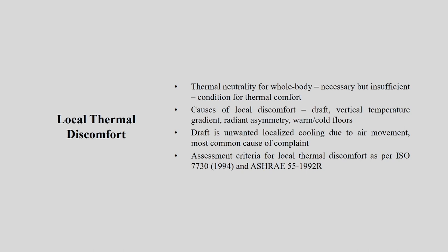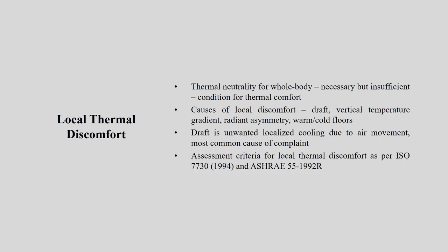Now, local thermal discomfort is also very important for us to understand, because in many cases we may not use PPD or PMV. So in those cases we use local thermal discomfort. So what is it? Thermal neutrality for the whole body is a necessary but insufficient condition for thermal comfort. So in those cases we use local thermal discomfort, and causes of local thermal discomfort may be draft, vertical temperature gradient.